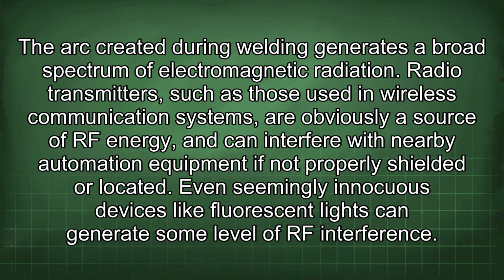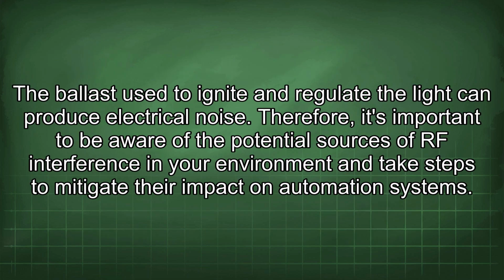Radio transmitters, such as those used in wireless communication systems, are obviously a source of RF energy and can interfere with nearby automation equipment if not properly shielded or located. Even seemingly innocuous devices like fluorescent lights can generate some level of RF interference. The ballast used to ignite and regulate the light can produce electrical noise. Therefore, it's important to be aware of the potential sources of RF interference in your environment and take steps to mitigate their impact on automation systems.